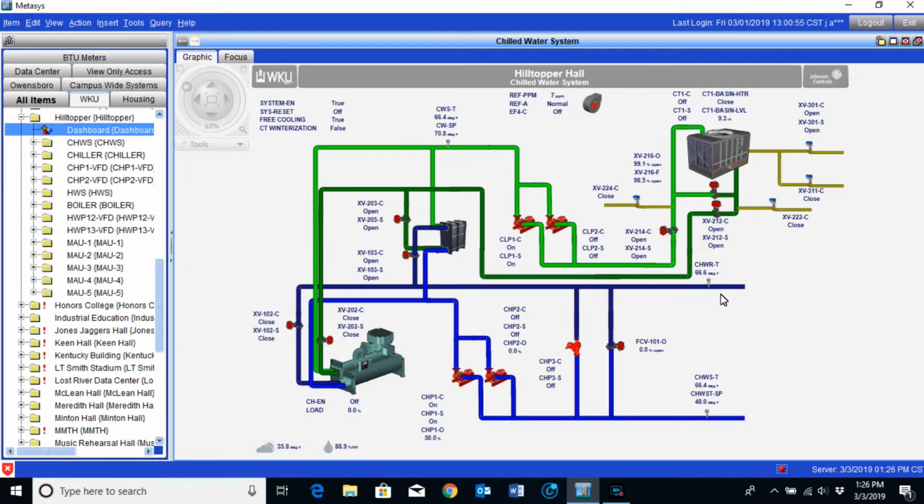When we get down into the 50s and below, we do have some locations where those units still need to have chilled water, and we cannot run a chiller for obvious reasons. If it is extremely cold outside, we cannot run a chiller, so the plate frame is the option that we will go with.